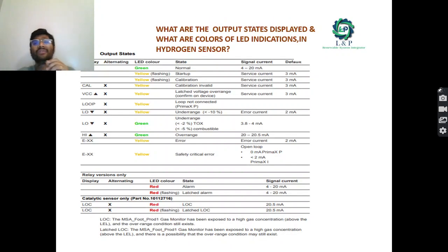And what are the different output states that will be displayed, and how can you identify them through the LED color indication inside the hydrogen sensor? If it is green, it is in normal operation. If the yellow is flashing at startup and keeps on flashing, it means calibration is happening. If the display is showing cal and the yellow is displayed, it means calibration is invalid. If it is showing VCC with an upward arrow and the LED indication is happening, it means latched voltage overrange, which it confirms on the device.